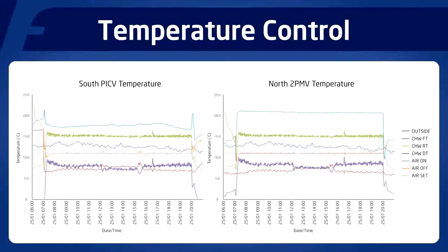These two graphs represent the temperature of the supply and return water and supply and return air, together with the outside air temperature. The left hand graph, we can see that the incoming air onto the air handling unit on the south riser is lower than the incoming air onto the air handling unit on the north riser.